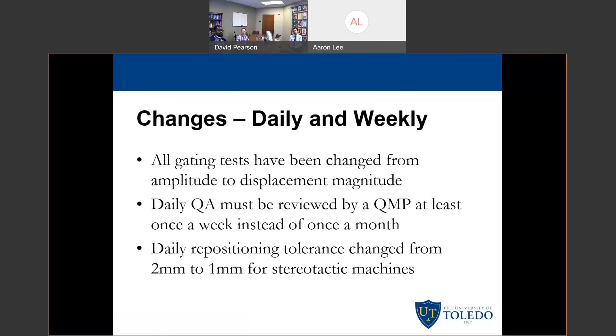Highlighting some of the more important changes — these are not every change that occurred between TG-142 and TG-198, but the ones identified as most important or most relevant. First, they decided to change all gating tests to be amplitude — or rather, change from amplitude to displacement magnitude. Before, you could do things in terms of relative percentage of gating, such as between 70% and 30%, instead of gating between 1 and 1.5 cm.